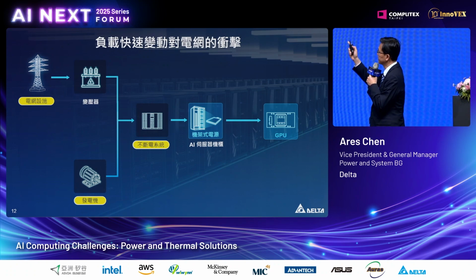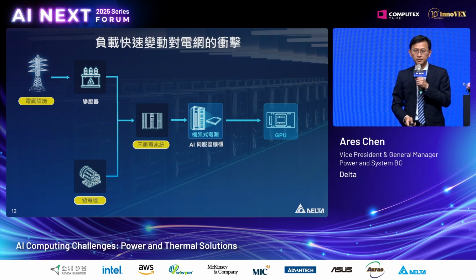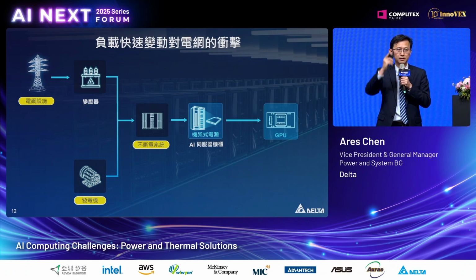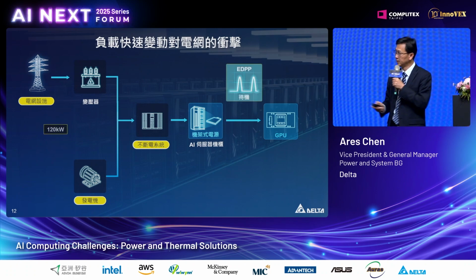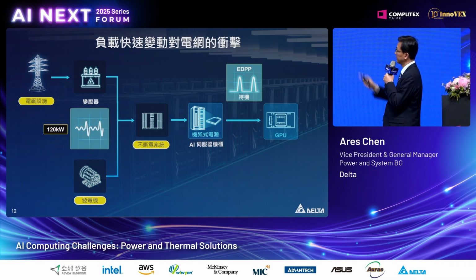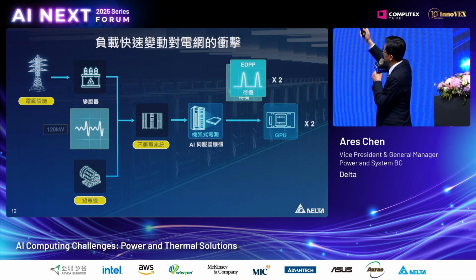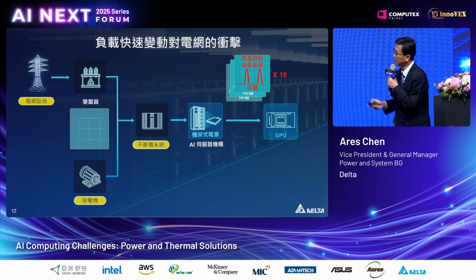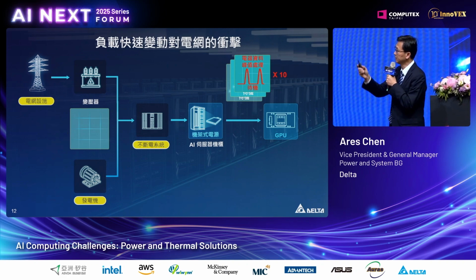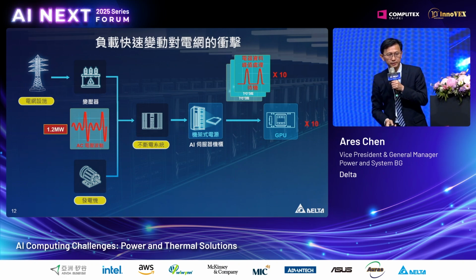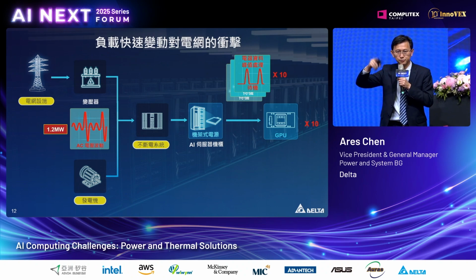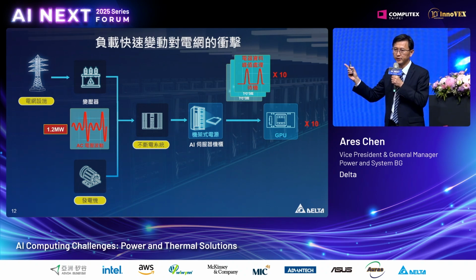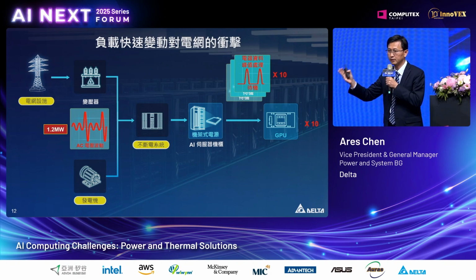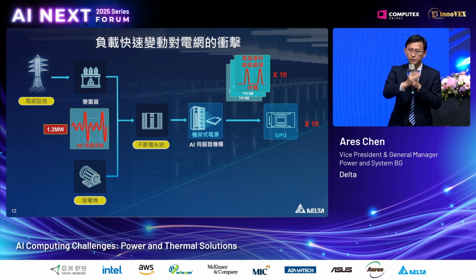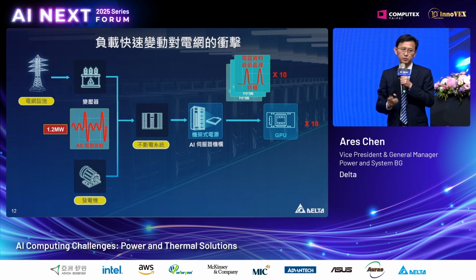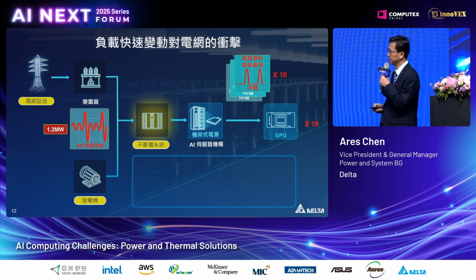Basically, it looks like this: that's grid, transformer, UPS, power generators, and AI server rack. So one rack is 120 kilowatts. Going through all of this, you will see 2 racks right here, 10 racks right here, and the load is changing rapidly. So you will see that the power fluctuation is reflected in the grid, and the grid cannot keep up.